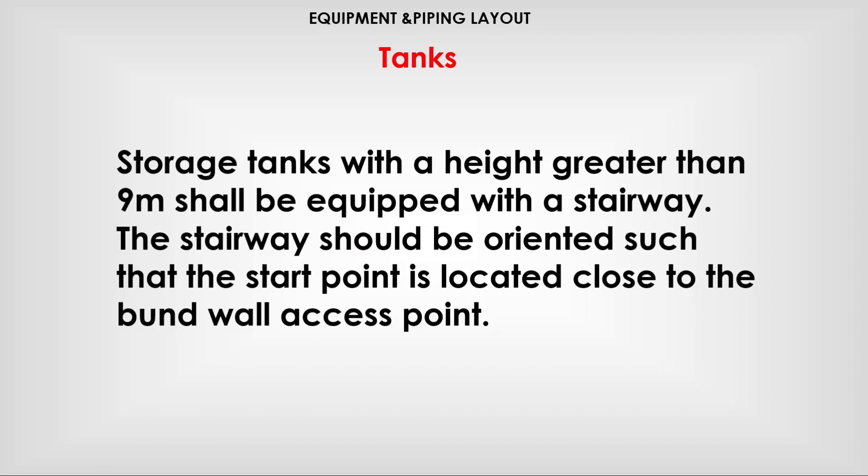Storage tanks with a height greater than 9 meters shall be equipped with a stairway. The stairway should be oriented such that the start point is located close to the bund wall access point.